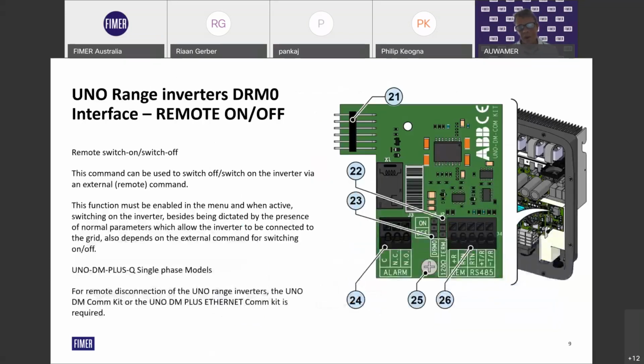But what I'll talk about, being from FIMER, is more at an inverter level, on how the remote on-off function works and how we activate the DRM0. So what you see here, I'll talk about the UNO range single-phase inverters first. When installing a UNO DM plus Q single-phase inverter, to meet this standard, you will require the optional COM kit. Now, FIMER offer 2 COM kits. The functions that you see on the screen here are all common to both. The common Ethernet COM kit has an RJ45 plug to it. So if Wi-Fi is not an option on site, you can hardwire through Cat5 Ethernet back to the customer's Wi-Fi.